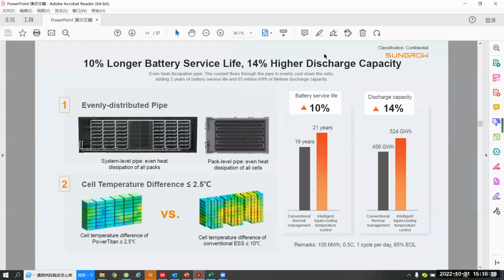The liquid cooling system uses evenly distributed pipes, designed at both the system pipe level and pack level. This helps balance the temperature of each battery cell. Through this method, the system temperature difference can be controlled to less than 2.5 degrees. Since temperature is a key factor for battery life and performance, this efficient temperature control can extend battery service life by 10% and increase discharge capacity by 14% for the ESS system.